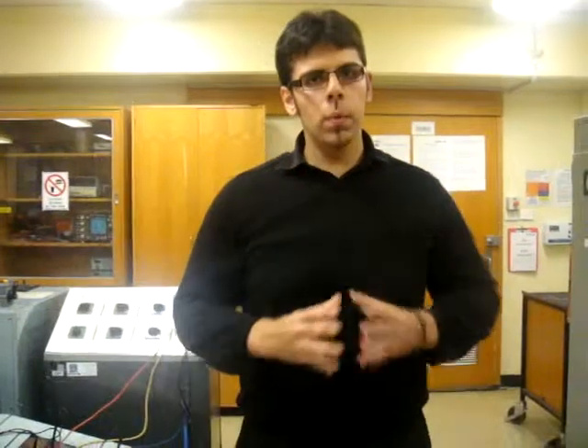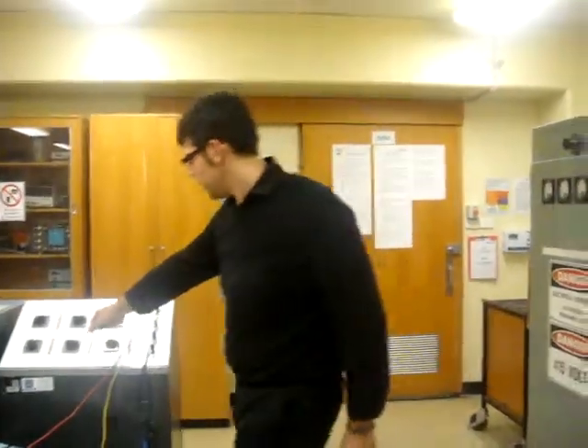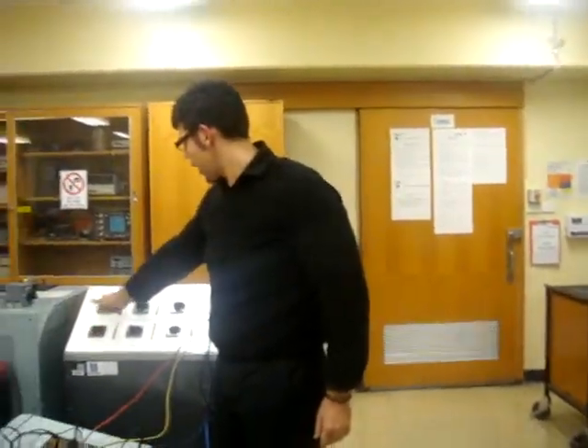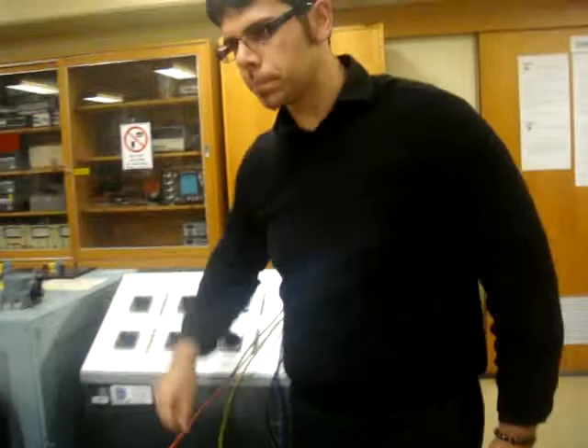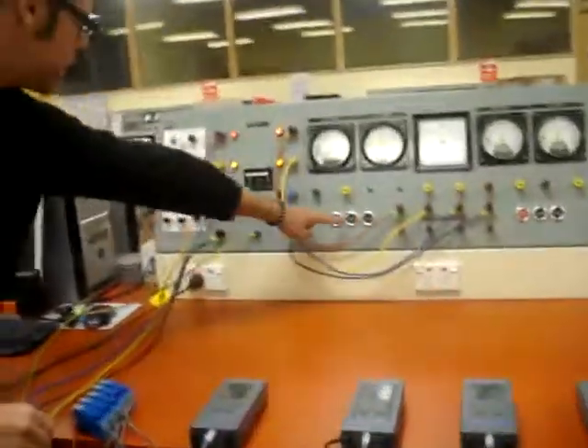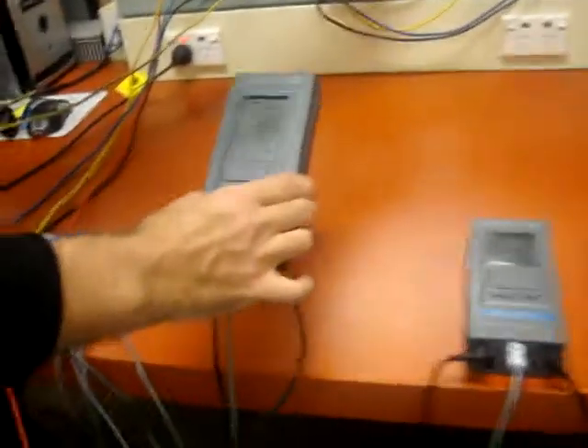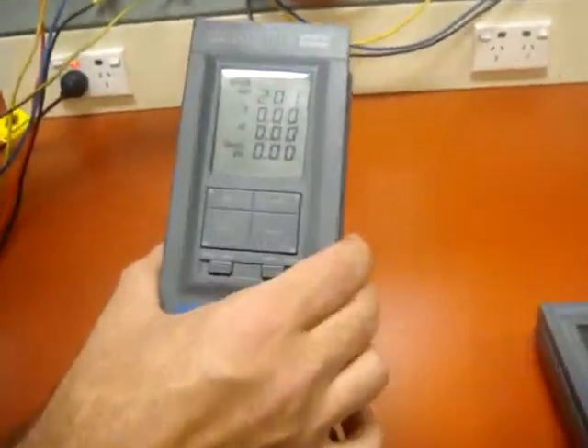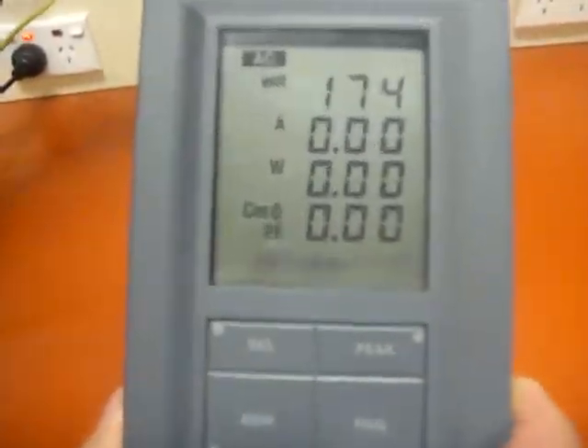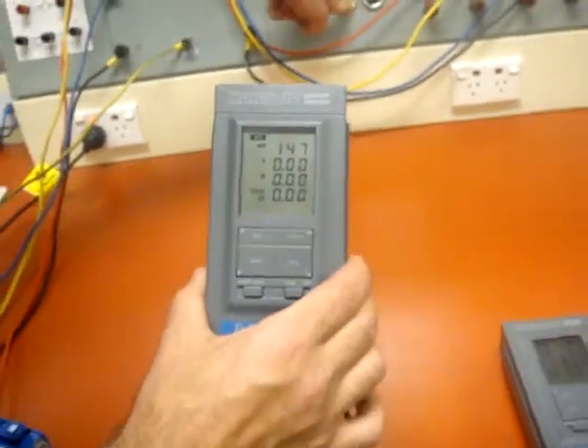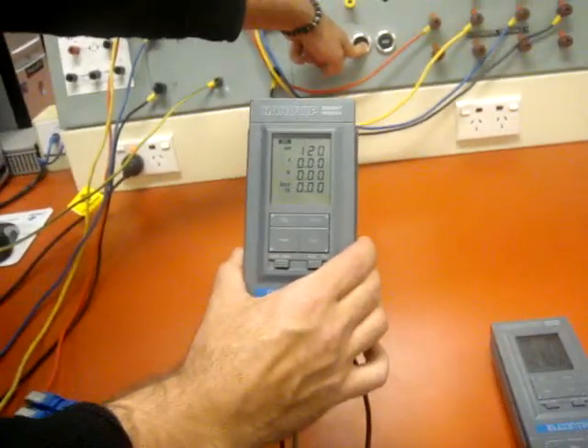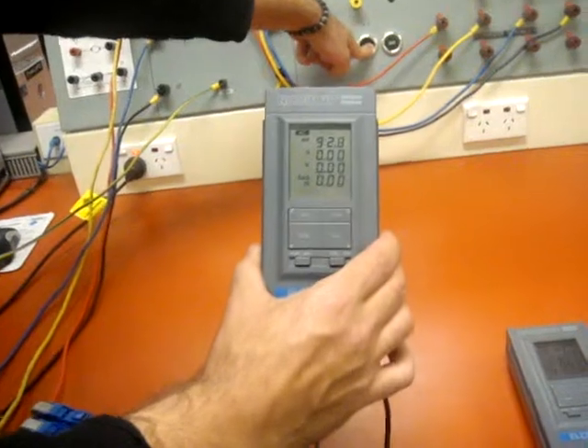Once again, we must now deactivate our power to our artificial transmission line. The first step is to turn off our load bank. We must then lower our voltage. Note that this is in a single phase configuration. That is why it is a lot slower to lower our voltage.